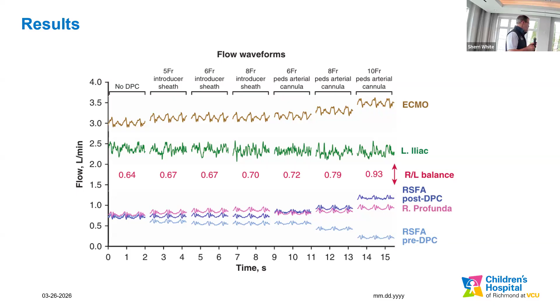So, discussion points from this article. Vascular introducer sheaths are, of course, commonly used as distal perfusion catheters for femoral veno-arterial ECMO. They're typically incorporated via the arterial cannula luer lock port with a short extension tubing connected to the sidearm of the sheath with a stopcock. What happens, though, is these small diameter connections were surmised to be the flow limiting points in the system.